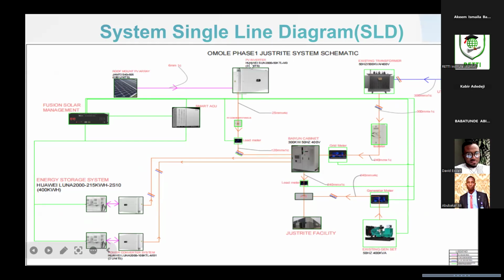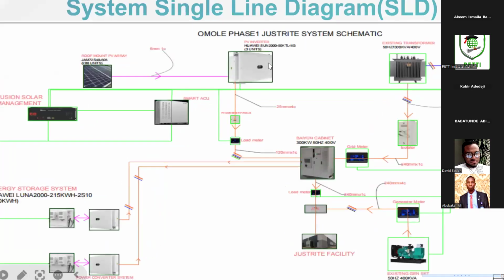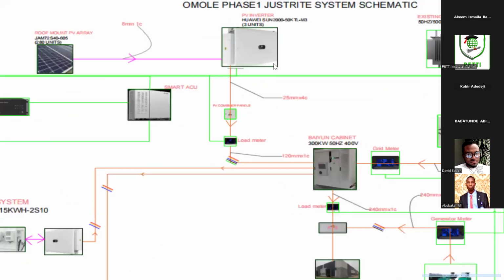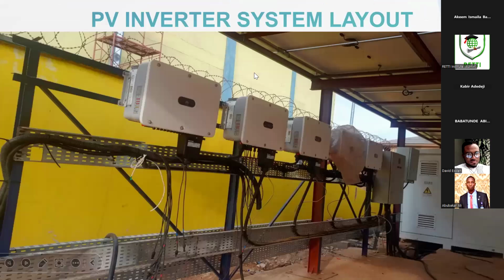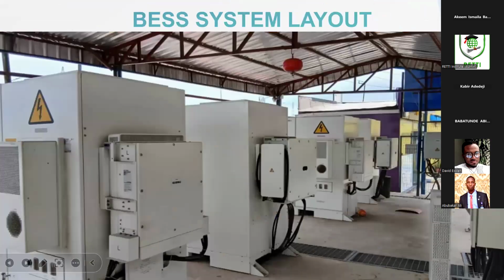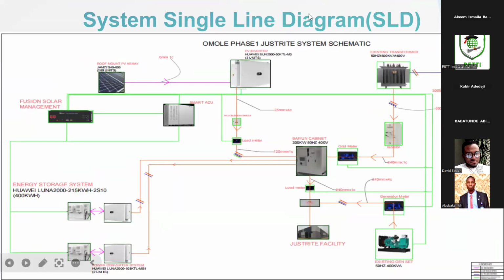The same thing with the PV inverter. For this system, how many PV inverters do we use? We use 3. You can also work this out yourself based on what I just explained. I mentioned something about 300 — this is 280 panels, which equals so many kilowatts. If you get the kilowatts, you can easily calculate how many PV inverters you need based on the analysis I just did.